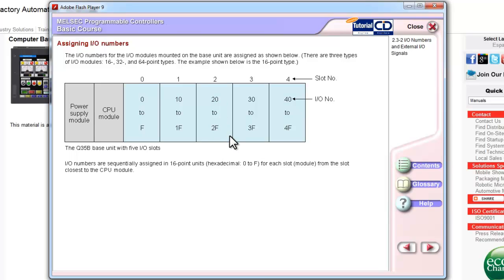IO modules come in either 8, 16, 32, or 64 point types. Also, with IO, you either have AC inputs or DC inputs. With DC inputs, you either have sinking inputs or sourcing inputs. Also, you have the option of selecting sink source inputs. For outputs, you have relay outputs, TRIAC outputs, or transistor outputs.